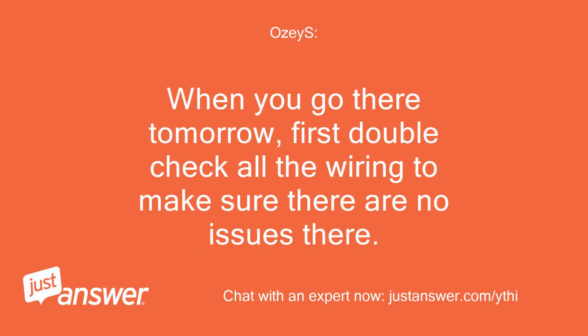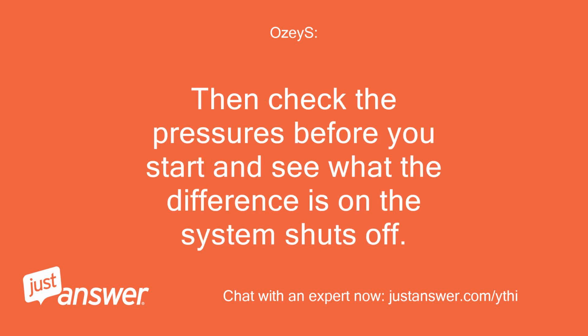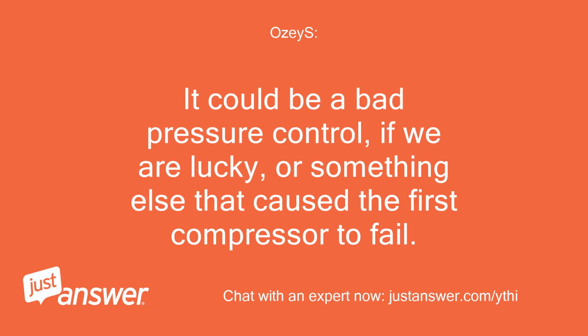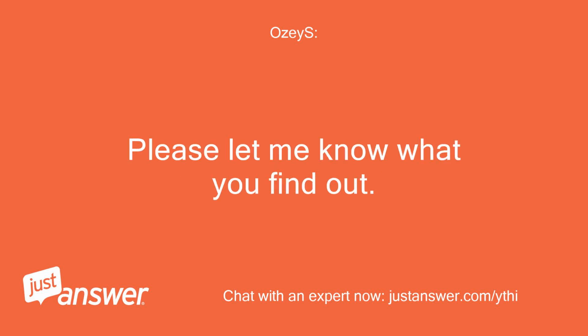When you go there tomorrow, first double check all the wiring to make sure there are no issues there. Then check the pressures before you start and see what the difference is when the system shuts off. It could be a bad pressure control, if we are lucky, or something else that caused the first compressor to fail. Please let me know what you find out.